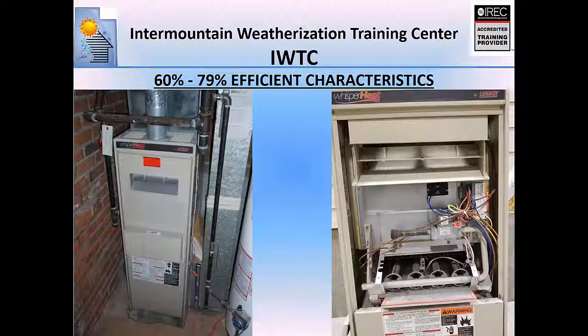It's kind of hard to see in this picture, but we've got this aluminum pipe running from the gas valve down to the burners. That's the standing pilot. That's part of the reason why this is only rated around 60% efficiency, because of what's lost due to the standing pilot.